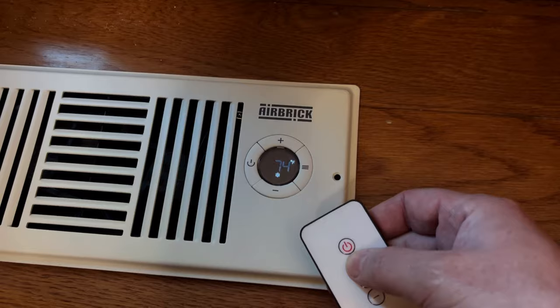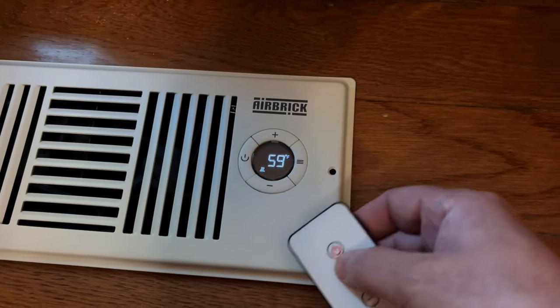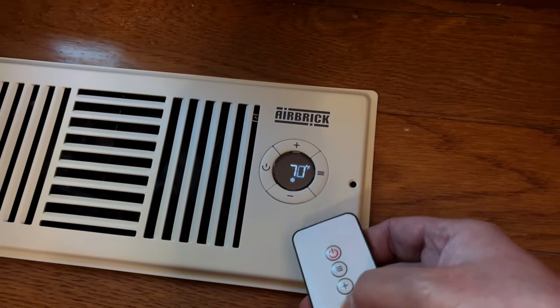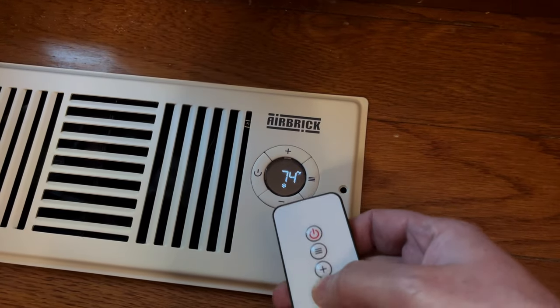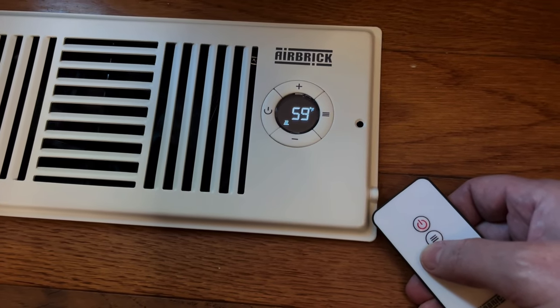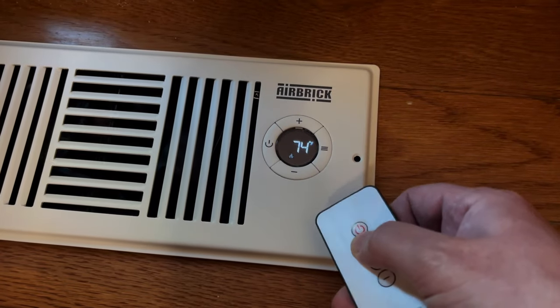Now let's go to the next one — this is the cooling trigger. This displays when it's time for the air conditioning; it pops on when you set it to that temperature. For example, you can have it automatically come on when it reaches 70 degrees. Once it reaches that temperature, that's what it's going to do. It displays the temperature at which the fan will turn on when the air conditioning system is running.